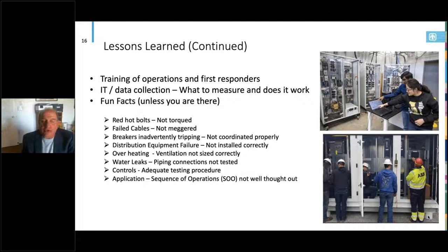Overheating of systems because we didn't have adequate ventilation. Water leaks, as I mentioned, piping connections not tested. Controls - adequate testing procedure, making sure you're checking everything, because one bit out of sequence in a register could drive you nuts.